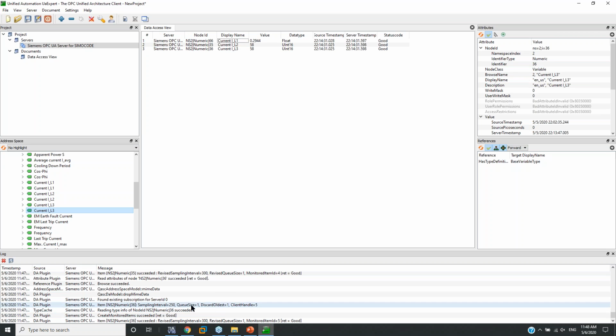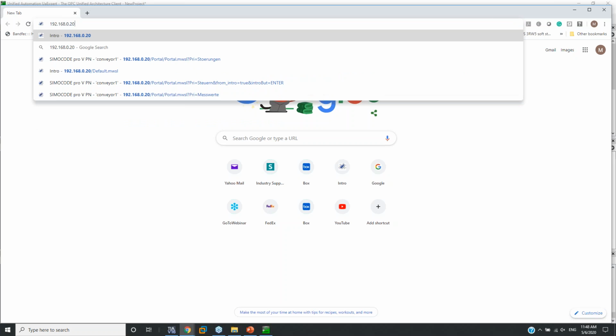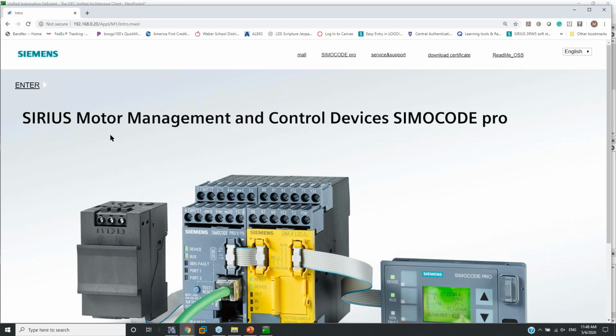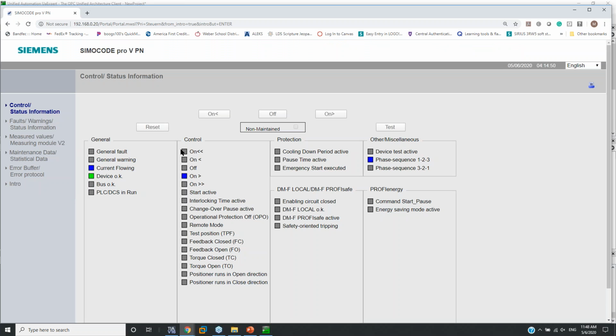Okay? All right, next item I want to bring up is that I'm going to now open up the web page to the SIMOCODE. And there's the web page for the SIMOCODE. Your maintenance guys don't need really any software once it's commissioned. All they need is the web page and access to the network that the SIMOCODE's on. Now this is for Profinet SIMOCODE and Ethernet IP SIMOCODE. Notice that my SIMOCODE's running. I can detect what phase it is. I can't change it, but I can detect. My device is okay, current's flowing, and it's all relative. We're going reverse or forward, whatever that is.